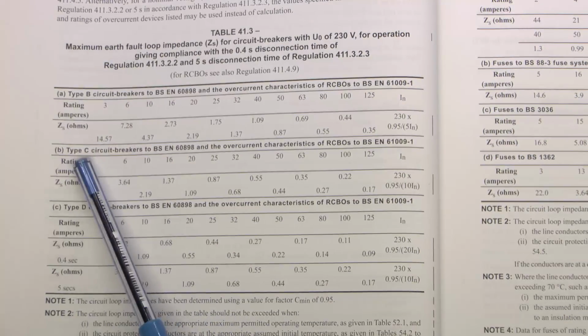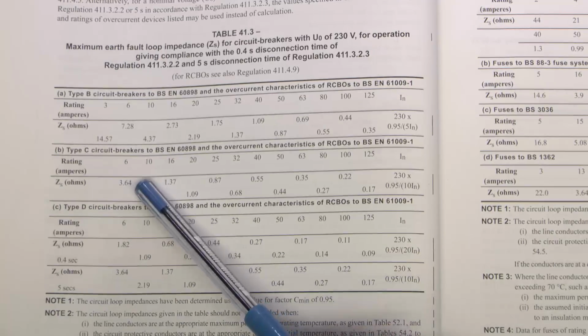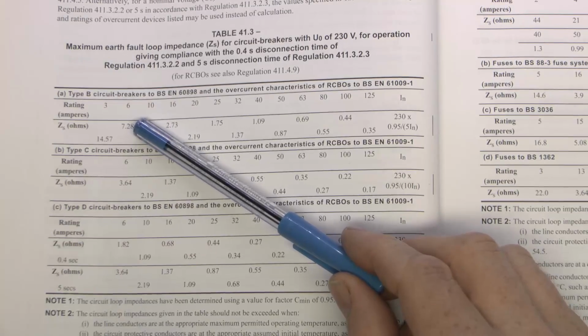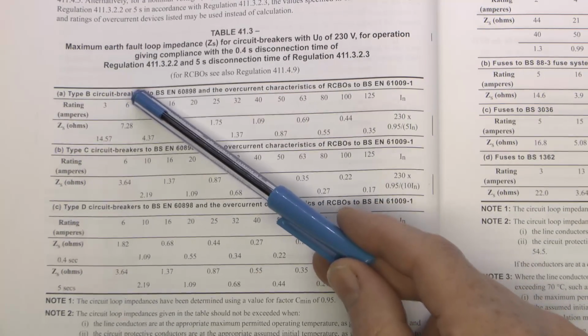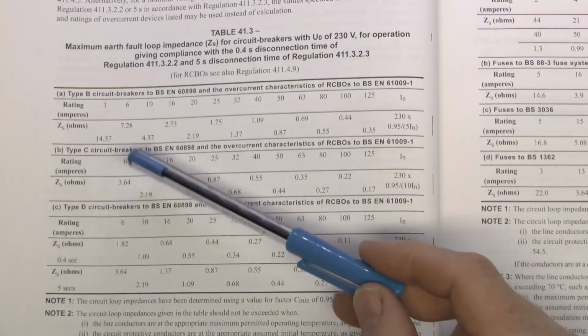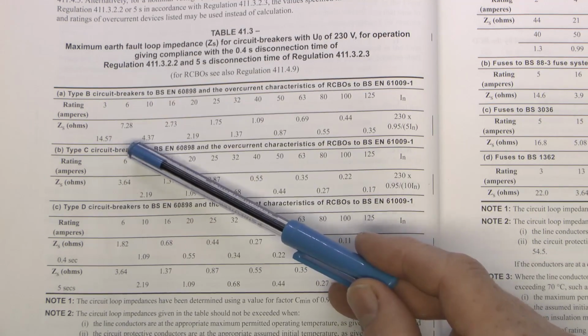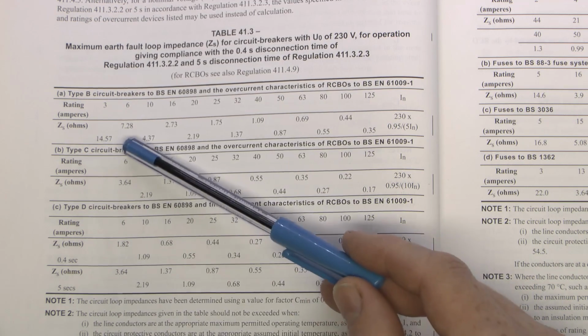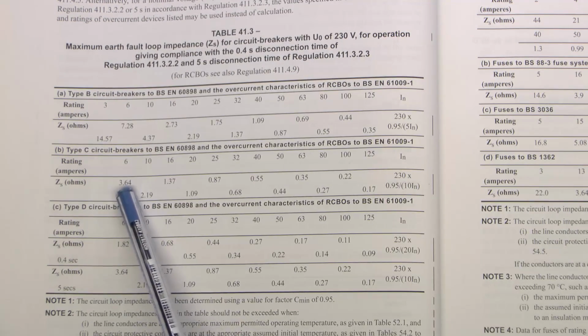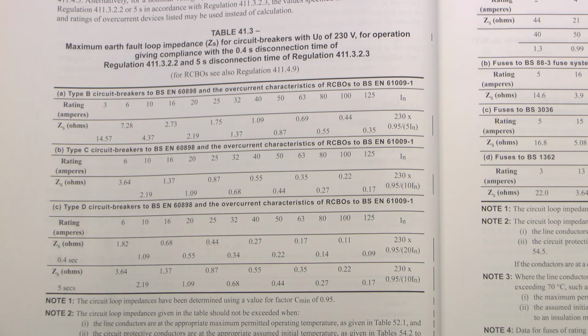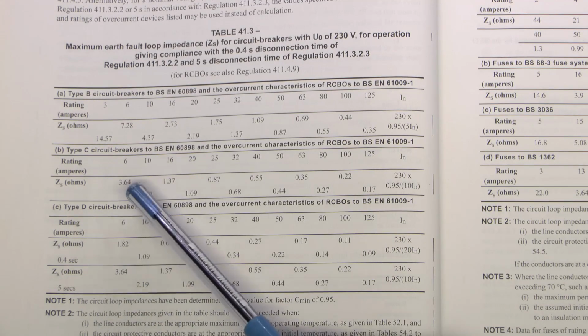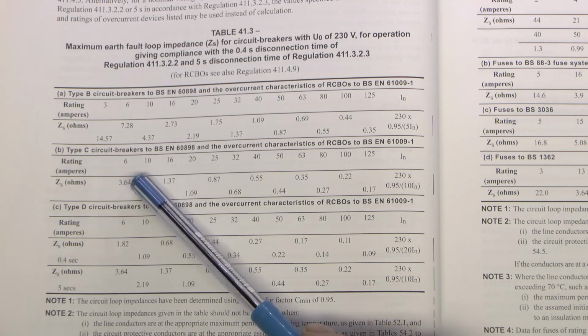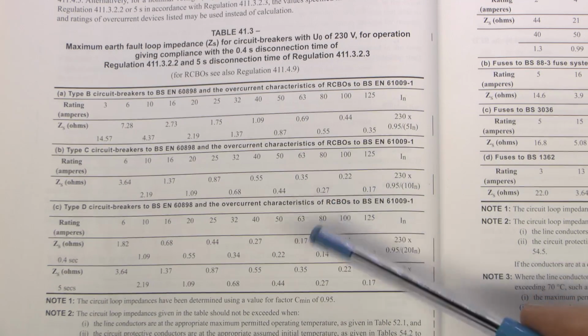But if you wanted to change to, say, a type C, then the maximum impedance is only 3.64. And you'll notice that 3.64 is actually half of 7.28. And of course the reason for this is this thing will trip up to a current of 5 times. This thing will trip up to a current of 10 times. So you need twice as much current to trip the type C. Therefore you need half the impedance to get the same amount of current. And conversely, if you move up to the type D, again the 6 amp one here, we'll find that the impedance is actually even lower. And again, it's half again, because you're going from a 10 times current here to the type D, which as seen previously requires 20 times.